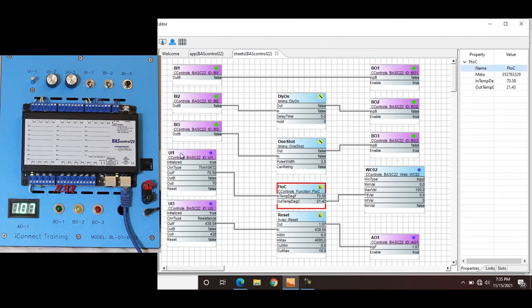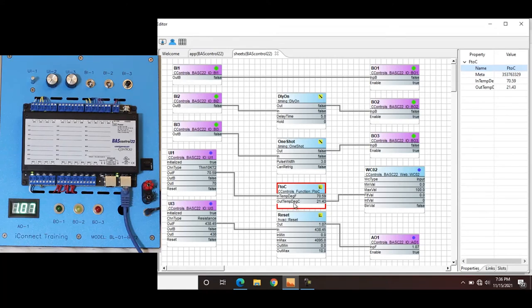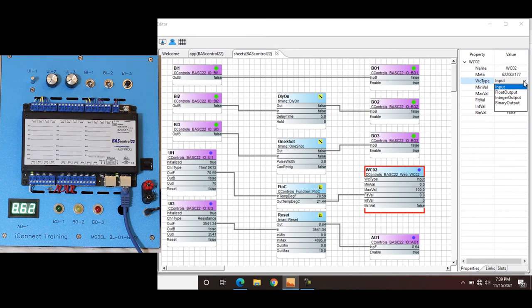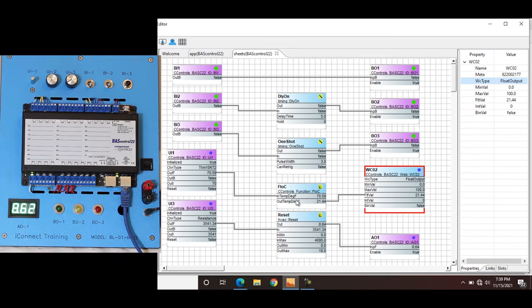Universal input 1 has an out of Fahrenheit and it's feeding to the FTOC — which is Fahrenheit to Celsius. The in temperature is degrees Fahrenheit: 70.58. And the output temp degrees Celsius is 21.43. For web component, we're going to change this to a float output, and now you can see it's registering the out temp degree Celsius float value: 21.44.